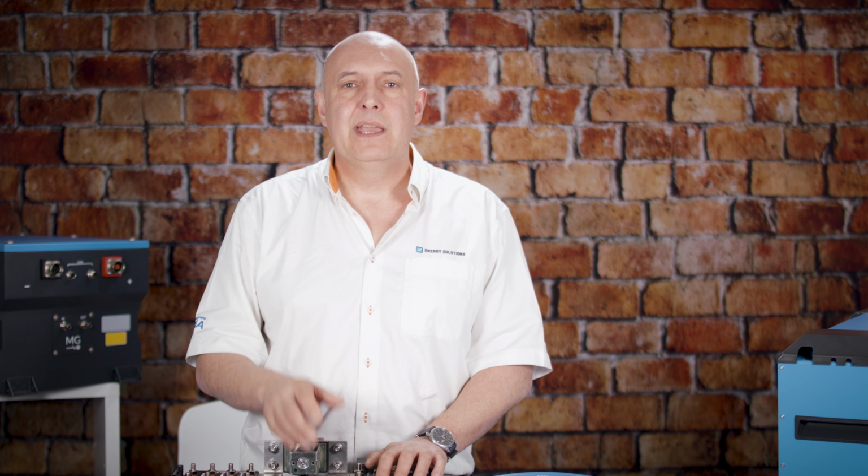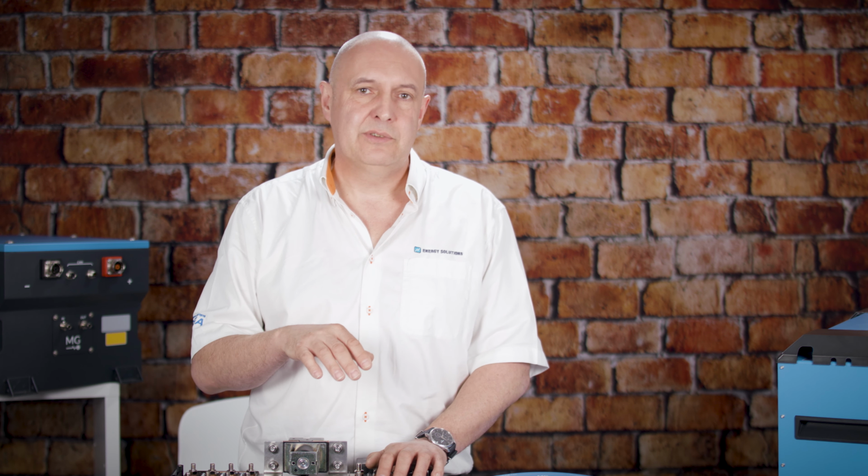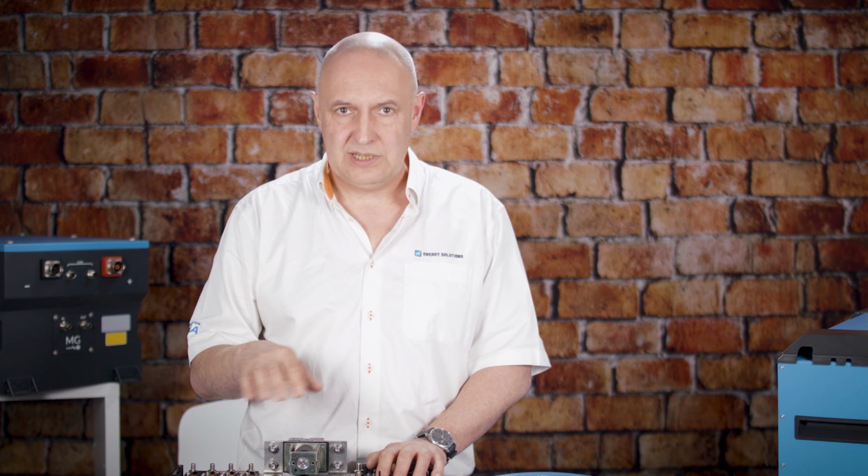So a good example of that instantaneous rating would be starting up pumps and motors and things like that, or short duration loads like thrusters in a marine application, and then you'd be falling away to limited duration, higher power loads rather than continuous. So microwaves, kettles, generally heating loads that would be on for a matter of minutes. Well, we can support those at a higher level than our 0.5C, and then we're really looking at our 0.5C being our background loads, which would generally be lighting, potentially a bit of air conditioning, that type of consumer.